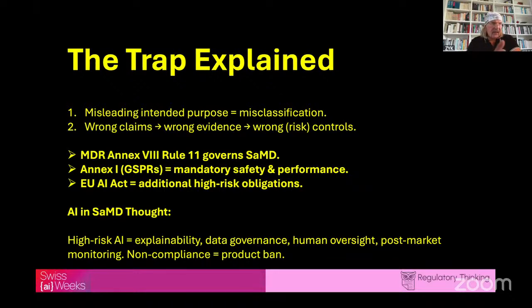activities. If you have a clinical claim with your product, then you must be aware that you are under the medical device regulation. And here the starting point is Annex 8 of the medical device regulation, where the medical device regulation gives the classification rules for medical devices, and especially Rule 11 governs software as medical device with or without artificial intelligence functionalities. And something that is also often overlooked is that Annex 1, the general safety and performance requirements defined in the medical device regulations, are mandatory for every medical device, software or implant or equipment, with AI, without AI, because these general safety and performance requirements are dealing with the safety and performance of the device.